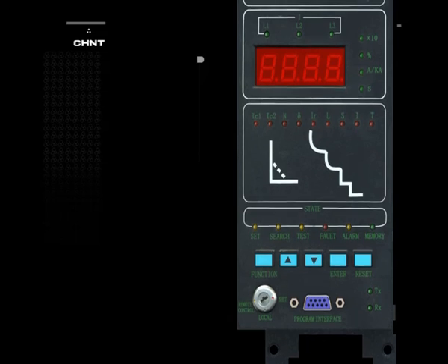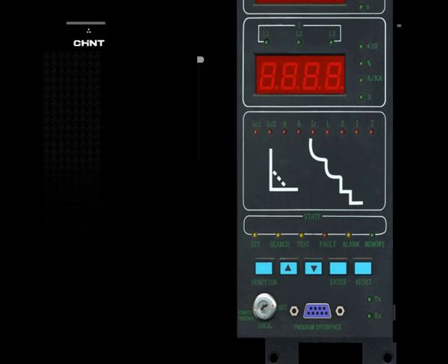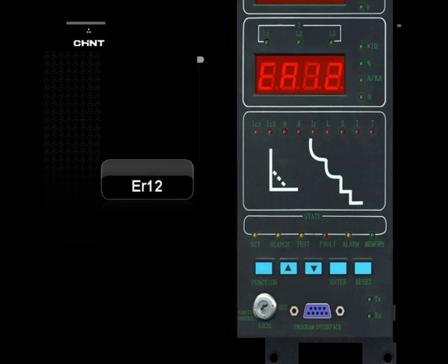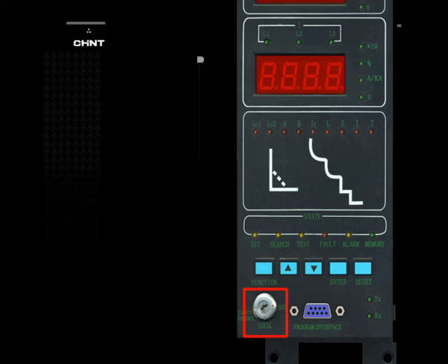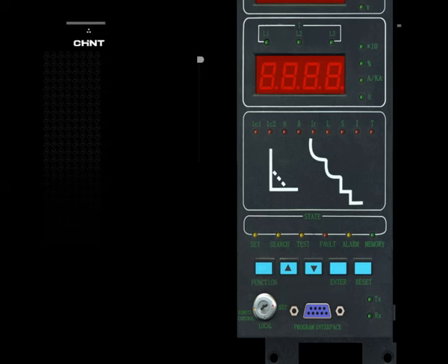Test of the H Controller: The test function performs a simulation test of the breaker's instantaneous tripping. The inherent operation time is displayed after the operation. If the breaker fails to break, ER12 is displayed. The key lock is at the set position; the function button is pushed until the test light flashes. The confirm button is pushed and the test light is constantly bright. Push the confirm button again and the breaker is cut, displaying the breaker's inherent mechanical operating time. The return button is pushed until the test light is off.